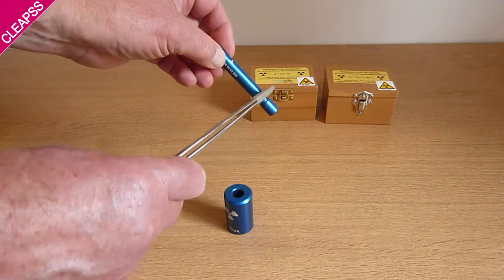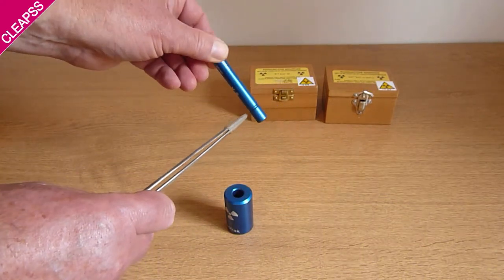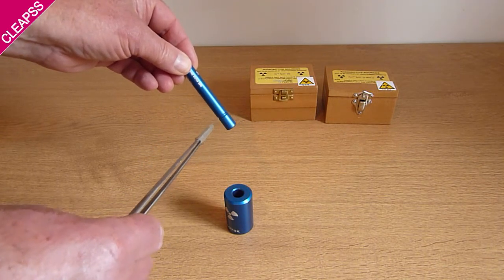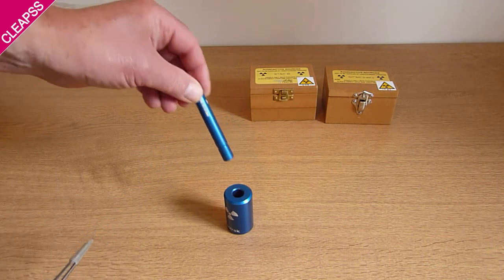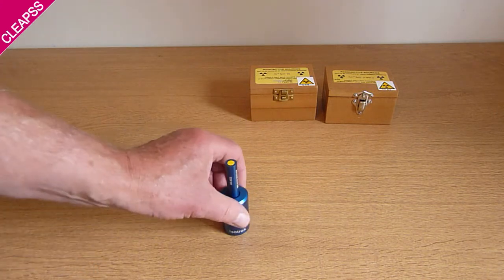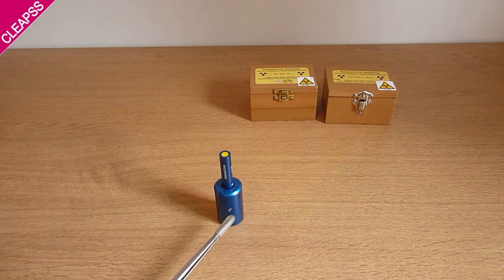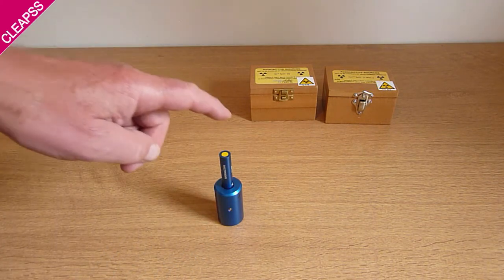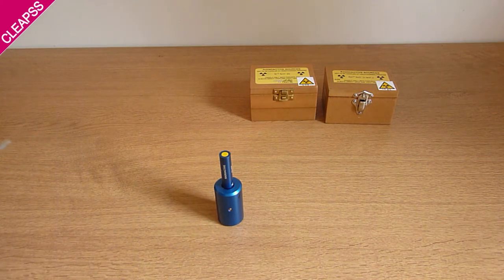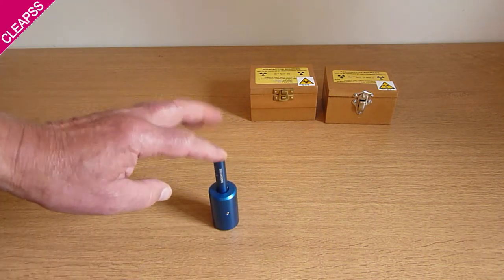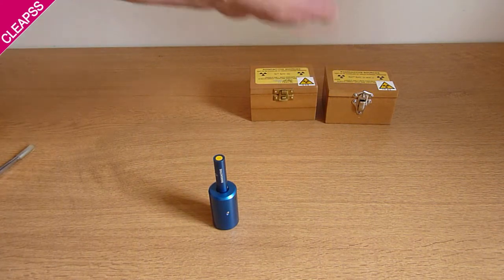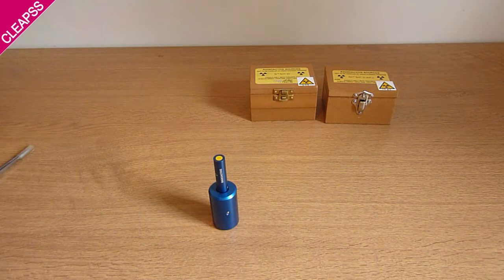The active end is indicated by the groove there. So you must make sure your hand is at the other end, well away from the active end. When you first buy these, a little screw on the back is screwed right in to lock the rod into the shield. You have to unscrew it a bit and adjust it so it clicks out and clicks in nicely. So that's the cup sources and the Isotrack source.